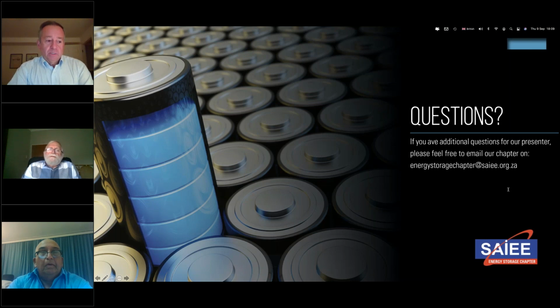Response time is important for ancillary services like frequency regulation. The inherent response time of the iron flow battery at the DC bus, where the reaction is happening, is very fast, like 10 milliseconds. What makes the system response about 1 second is the communication between the inverter and the BMS to get the battery to react to a command. That should satisfy most ancillary services out there. It obviously doesn't serve as a UPS seamlessly carrying a load, but for performing ancillary services for the grid, it's very capable.